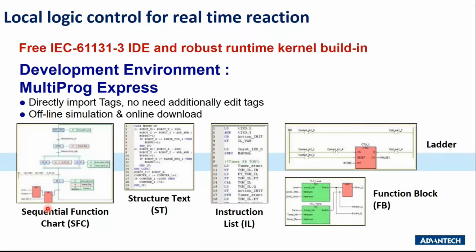Sometimes our calculation tag or computation may not meet your requirement. So we provide three different software programming options you can use on our hardware, our EdgeLink platform. One is IEC 61131, which is one of the standard PLC programming languages, right? You can use the PLC programming language to do process control, or certain computation needed by the project requirement. So this is one of the programming options.